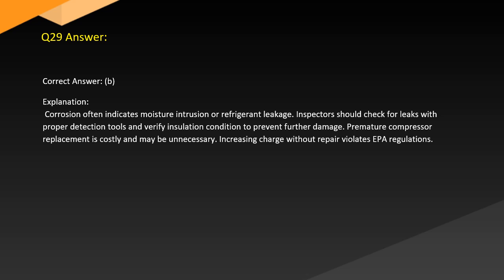Answer. Correct answer: B. Explanation. Corrosion often indicates moisture intrusion or refrigerant leakage. Inspectors should check for leaks with proper detection tools and verify insulation condition to prevent further damage. Premature compressor replacement is costly and may be unnecessary. Increasing charge without repair violates EPA regulations.